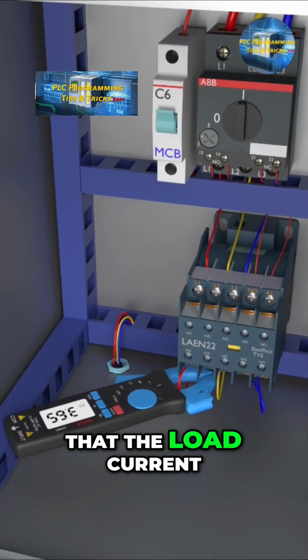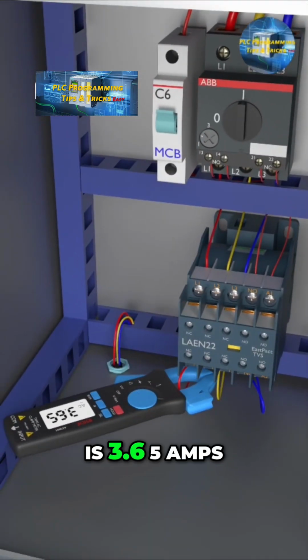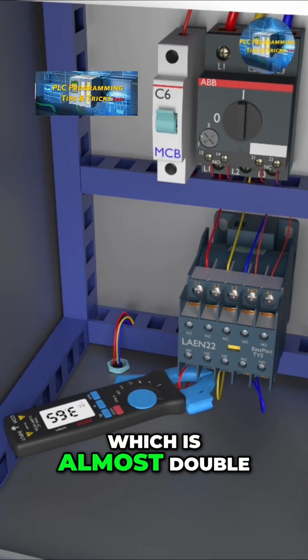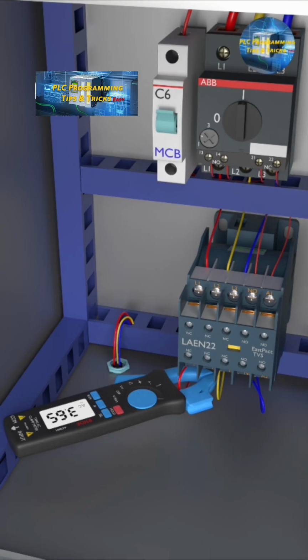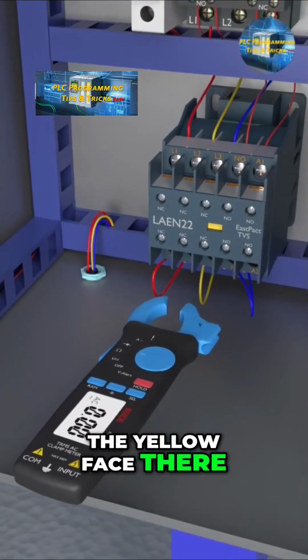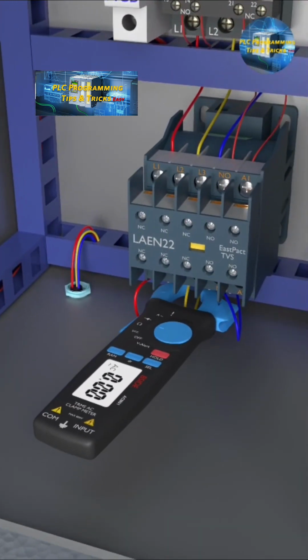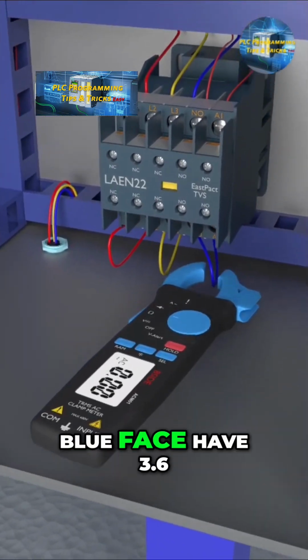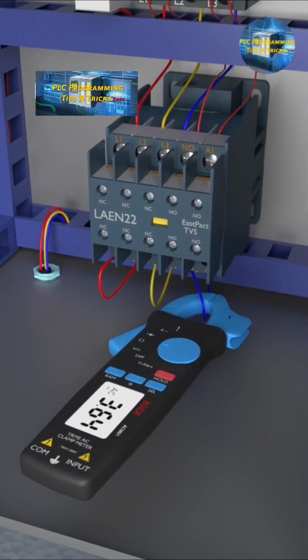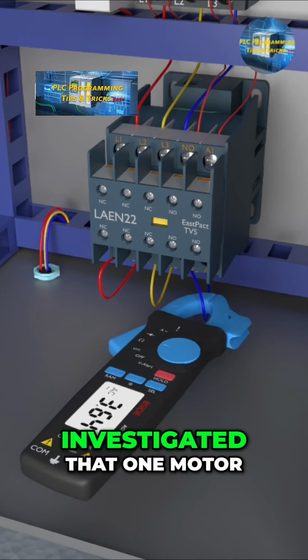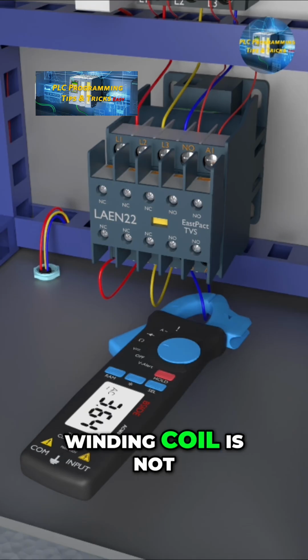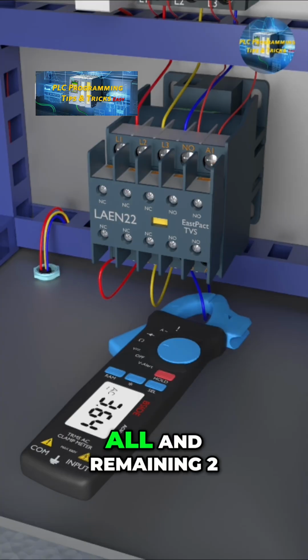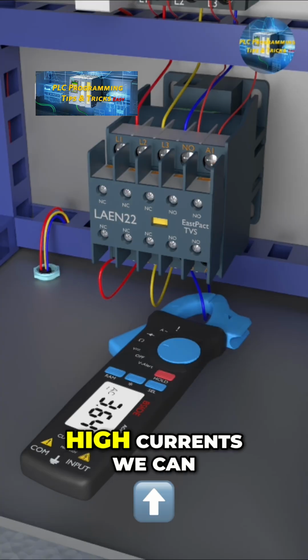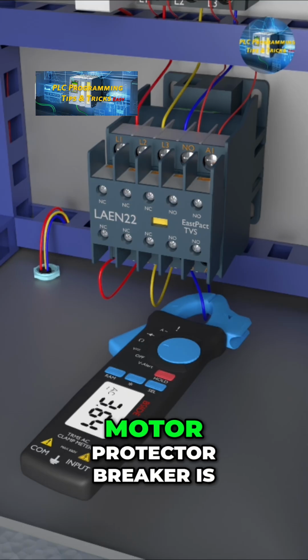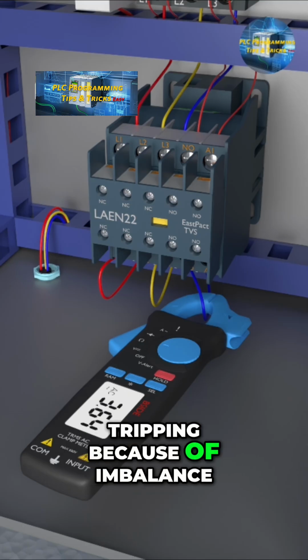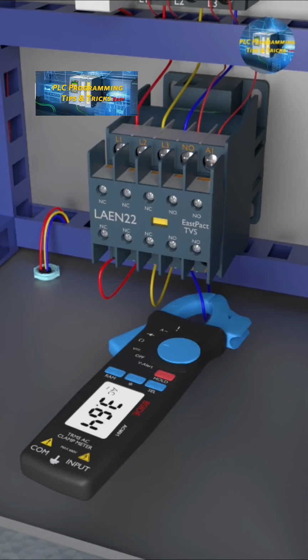As you can see, the load current on the red phase is 3.65 amps, which is almost double the motor rated amps. Now if we check the yellow phase, there is no load current at all. The blue phase has 3.65 amps load. So now we have found that one motor winding coil is not drawing current at all, and the remaining two coils are drawing very high currents. We can now conclude that the motor protector breaker is tripping because of imbalanced current in the motor winding coils.